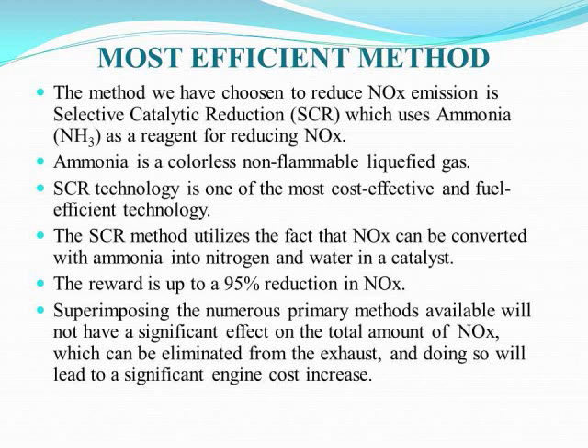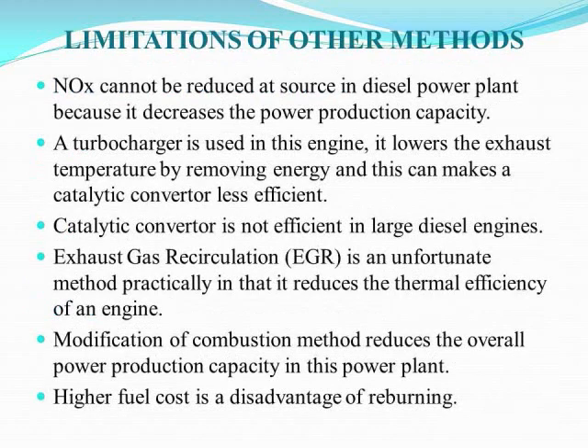The most efficient method we have chosen to reduce NOx emission is selective catalytic reduction (SCR), in which ammonia is used as a reagent. Ammonia is a colorless, non-flammable liquefied gas. SCR technology is one of the most cost-effective and fuel-efficient technologies, providing up to 95% reduction in NOx. Superimposing numerous primary methods will not have sufficient effect and leads to significant engine cost increases.